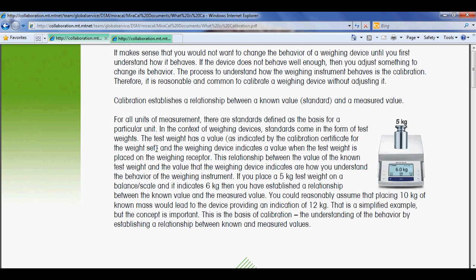Of course, in the context of weighing devices, our standards are in the form of test weights, certifiable test weights. The test weight has a value, and the weighing device indicates a value when that test weight is placed on the weighing receptor. This relationship between the value of the known test weight and the value that the weighing device indicates are how you understand the behavior of the weighing instrument.